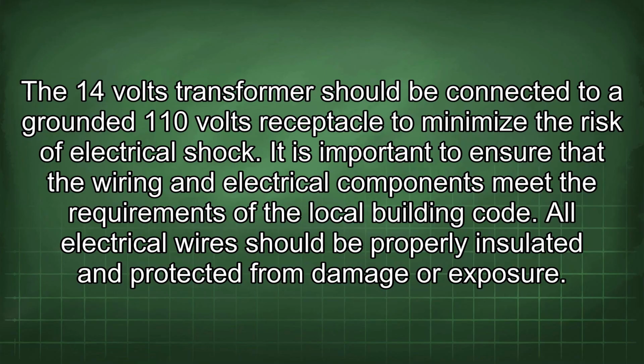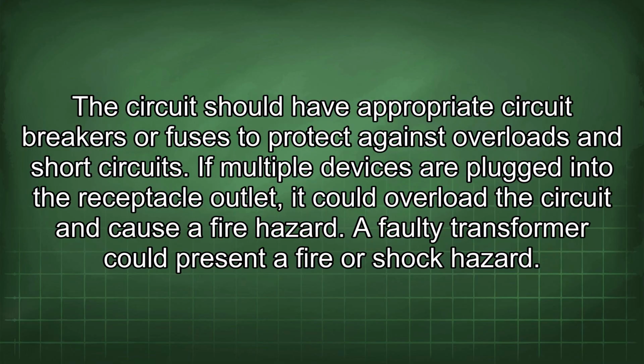The 14 volts transformer should be connected to a grounded 110 volts receptacle to minimize the risk of electrical shock. It is important to ensure that the wiring and electrical components meet the requirements of the local building code. All electrical wires should be properly insulated and protected from damage or exposure. The circuit should have appropriate circuit breakers or fuses to protect against overloads and short circuits.